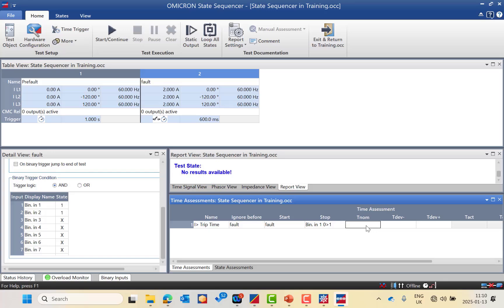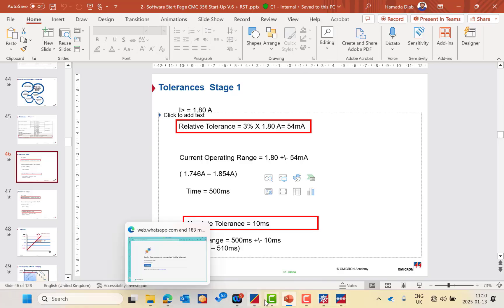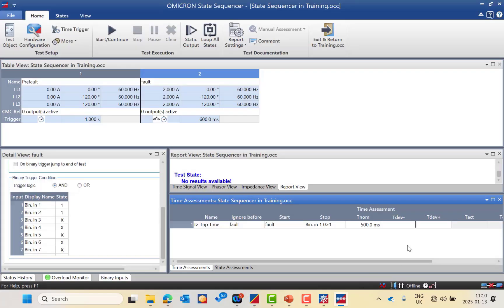Since I know the trip time is 500 milliseconds, I will enter it directly. Here is the T deviation plus or minus. From the presentation, the absolute error is ±10 milliseconds, so I will add 0.01 in both plus and minus fields. Based on this assessment, if the measured time is between 490 and 510 milliseconds, it will be assessed as passed; otherwise it will be failed.